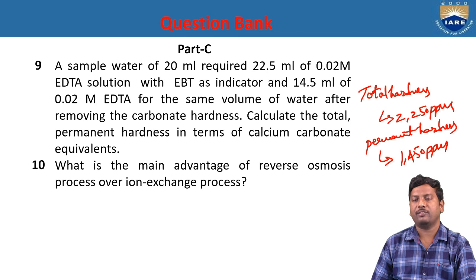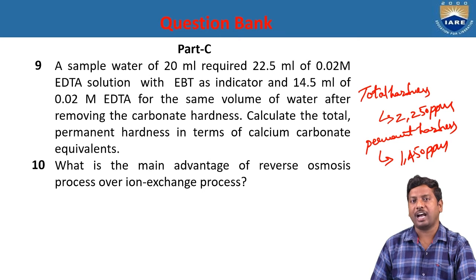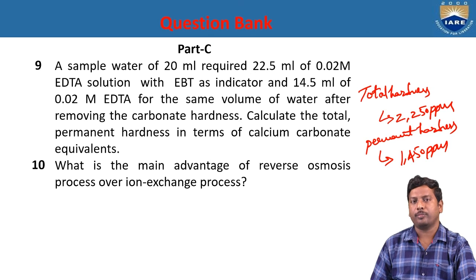What is the main advantage of reverse osmosis over ion exchange process? By using the ion exchange process we can remove both cationic and anionic impurities — that means impurities present in ionized form — but we cannot remove non-ionized impurities. By using reverse osmosis, we can remove both ionic and non-ionic impurities, and even silica and turbidity are also removed. Those are the advantages of reverse osmosis compared to the ion exchange process.